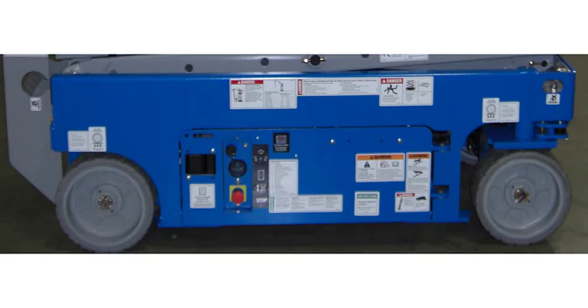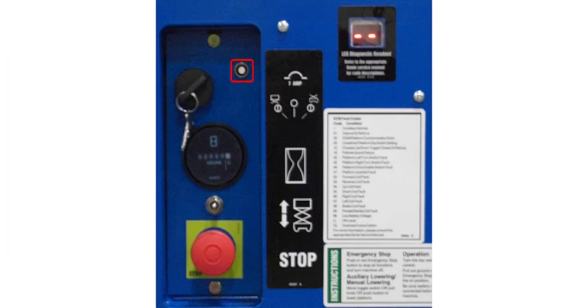The right-hand side of the machine houses the ground control panel and hydraulic reservoir. The following pages will show and describe the components located inside of the tray. The ground control panel houses a 7-amp circuit breaker that is in place to protect the electrical control system, a key switch to select platform operation, power off, or ground control operation, an hour meter that counts time while the electric motor is running, the platform up and platform down toggle switch, emergency stop button, and the LED display window and decal to explain fault conditions and codes.